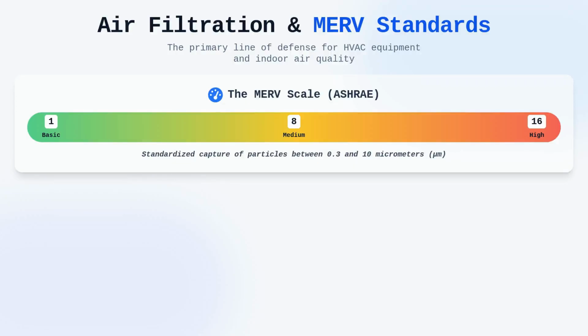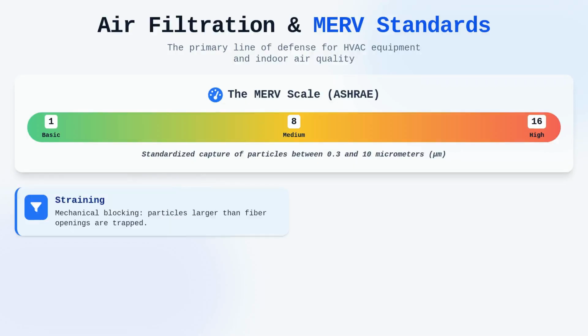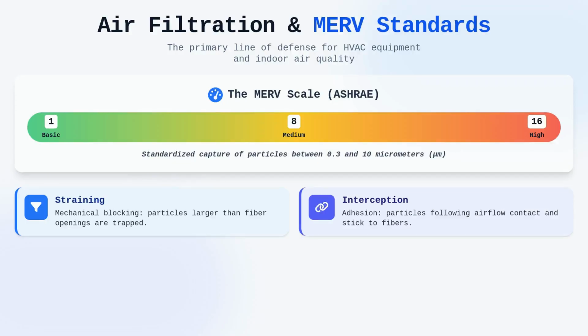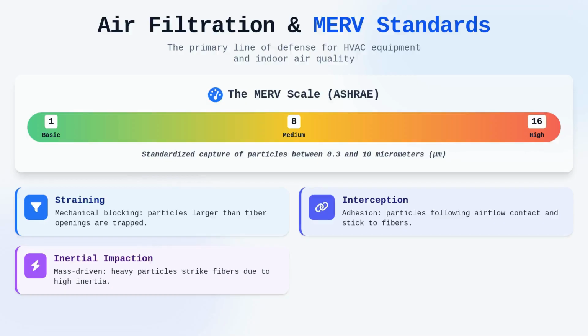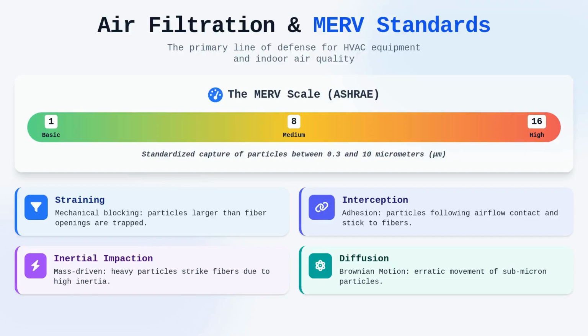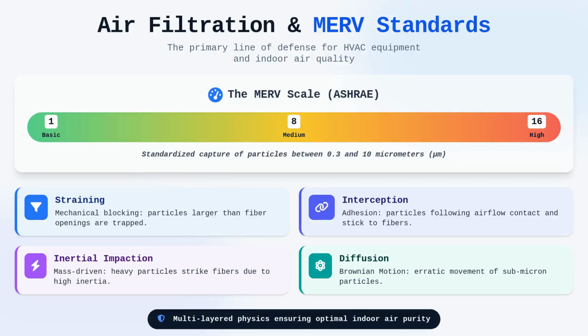When we talk about these filters, we are primarily dealing with the mechanics of how particles are trapped as air flows through the media. Straining is the simplest mechanism, where particles larger than the openings between filter fibers are mechanically blocked. Interception occurs when particles following the airflow path come into contact with a fiber and adhere to it. Inertial impaction is effective for larger, heavier particles that have too much inertia to follow the curving streamlines of air, causing them to strike the fiber surface. Diffusion acts on the smallest submicron particles, which move in erratic patterns due to Brownian motion, increasing their statistical probability of colliding with filter media fibers.